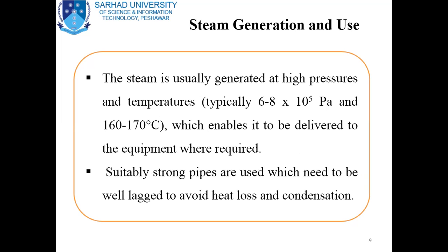The steam is usually generated at high pressures and temperatures, typically 6 to 8 multiplied by 10 to the power 5 Pascal, and 160 to 170 degrees centigrade, which enables it to be delivered to the equipment where required.